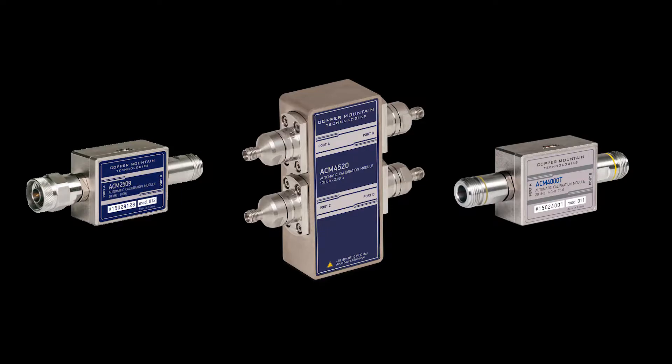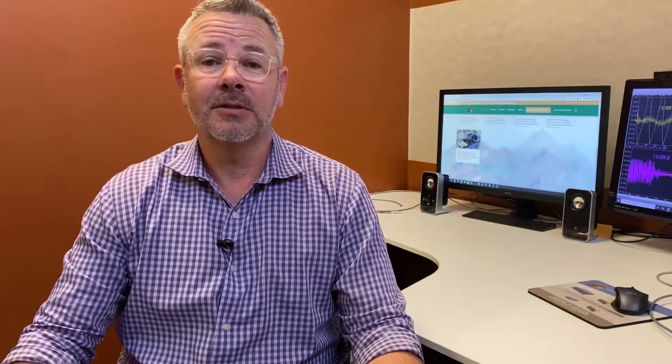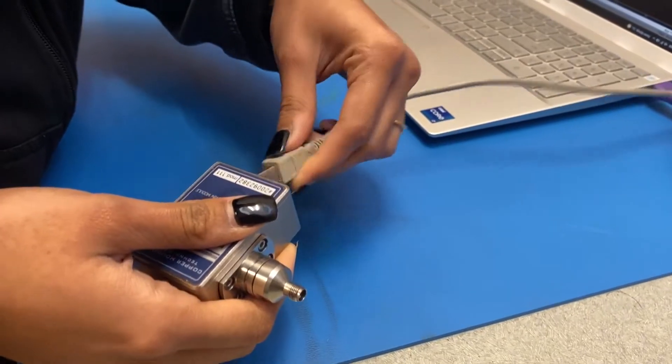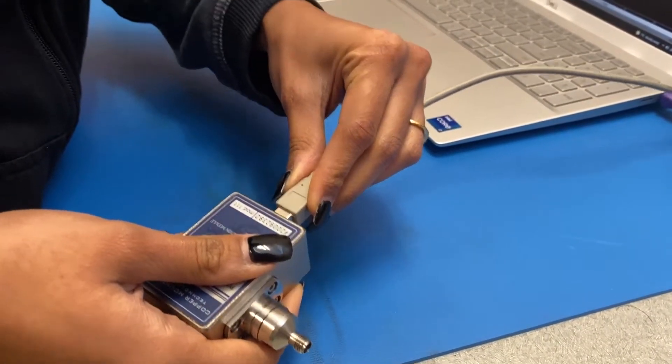We have both two-port and four-port ACMs available. To perform automatic calibration, follow these steps. First, connect the ACM to the PC using a USB cable.